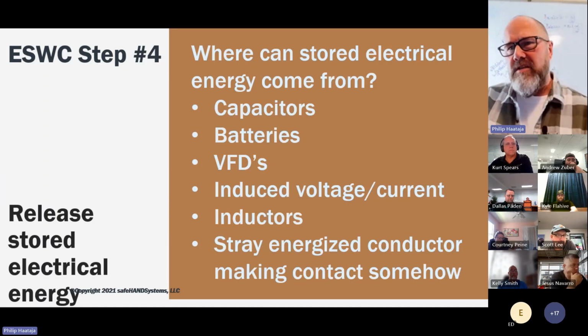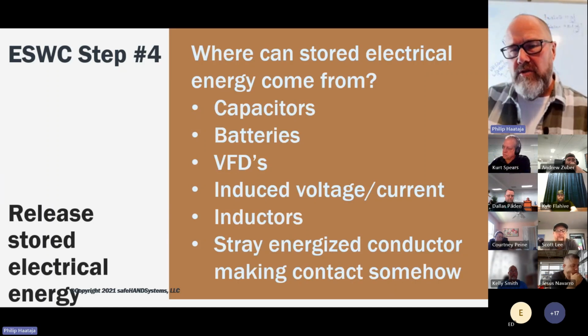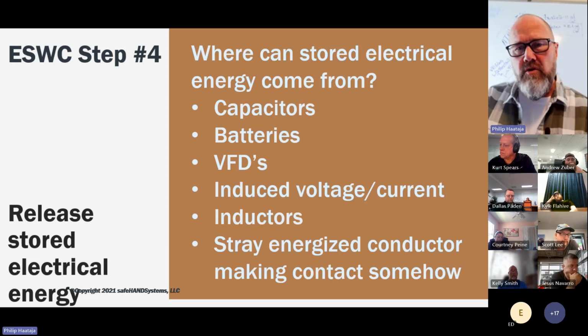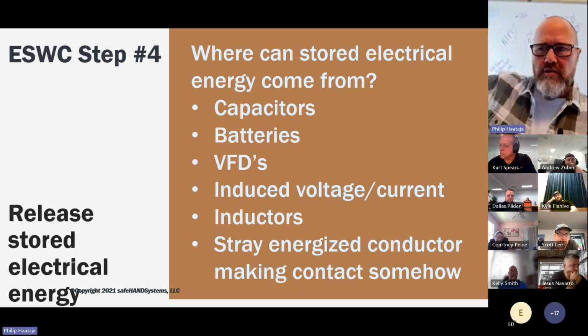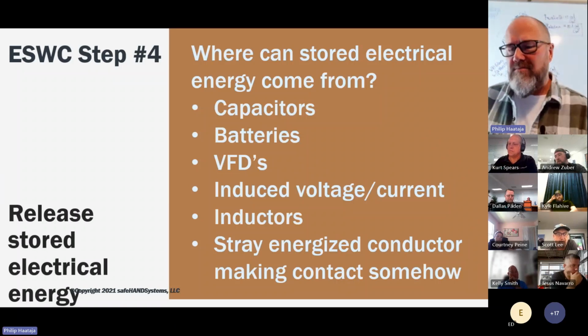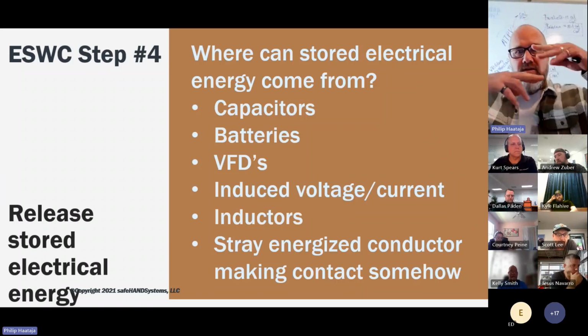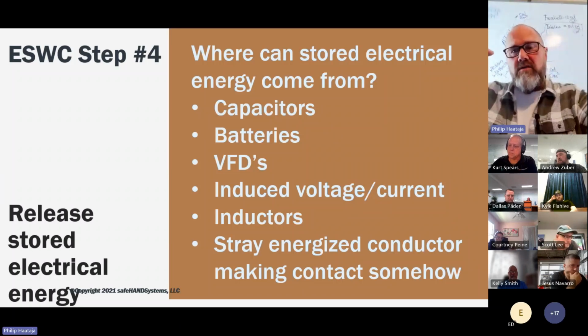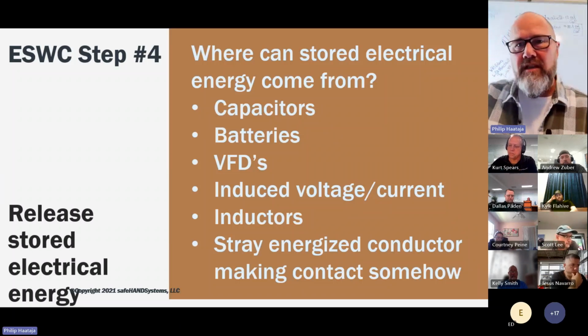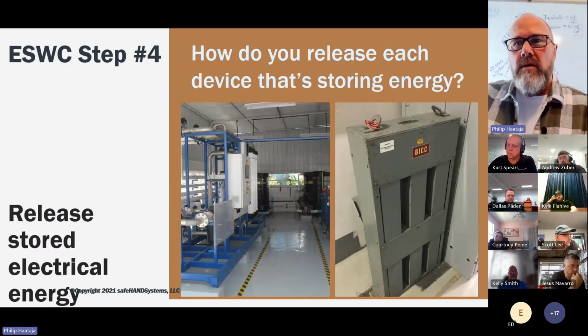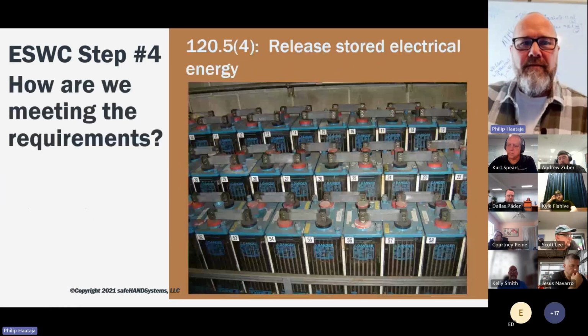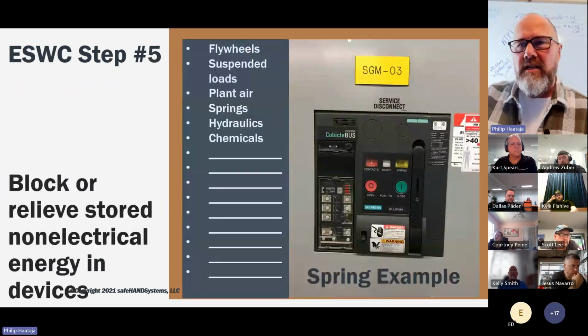VFDs, batteries, you could have some induced voltage. We talked about that fan example where the building was pressurized. You could have a pump somewhere that has pressure on some sort of pressure vessel, backfeeding or pushing through that. You could have parallel wire circuits inside a cable tray where yours is shut off and the other one's running. You could have backfeed induced voltage, kind of the electric fence example I gave you earlier.